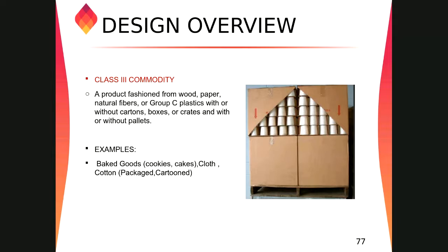Okay, so you can see after the class into the soft copy what types of the product comes under which commodity classification. Like for class 3 commodities, table 1.10 of your manual shows that we have food products, the frozen food products, flammable or combustible liquid, but that should be the aerosol only, level 1, furniture and bedding, housing materials, miscellaneous, plastic and rubber with some quantities.